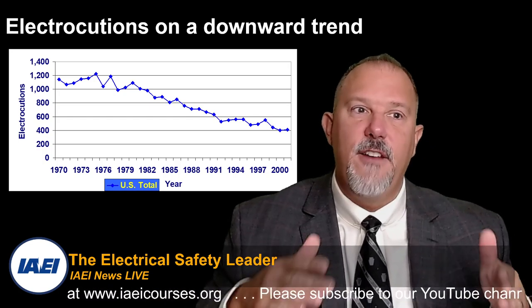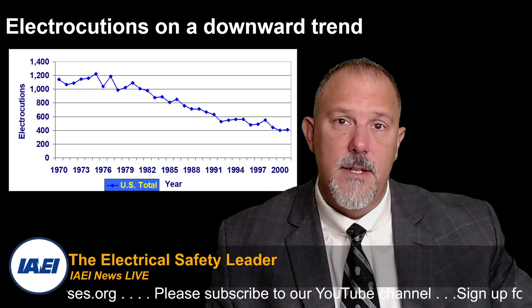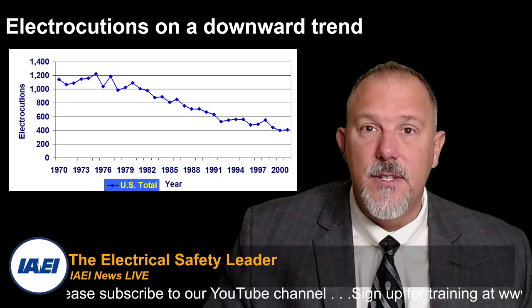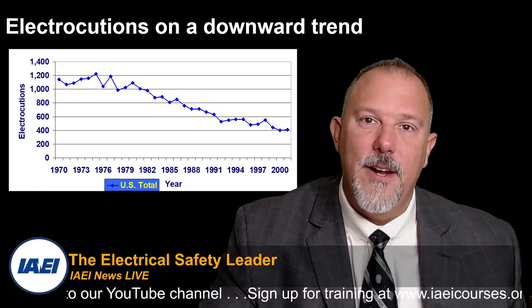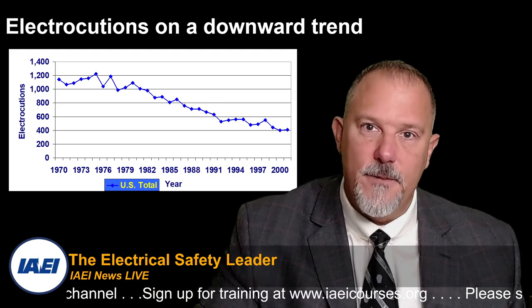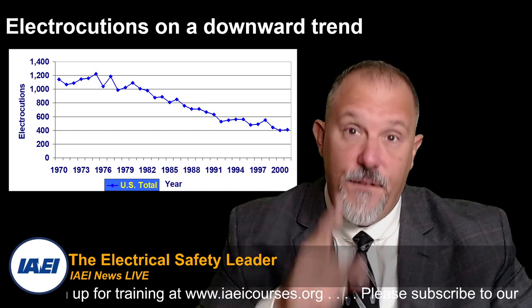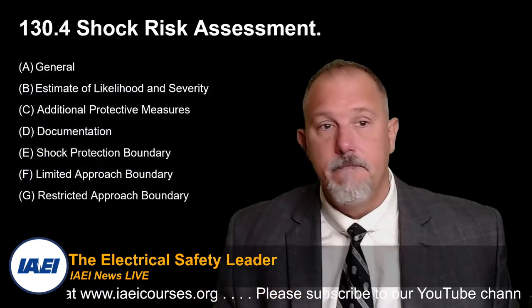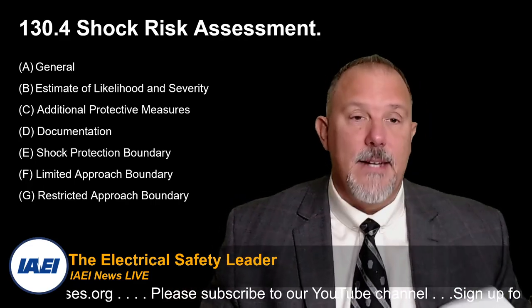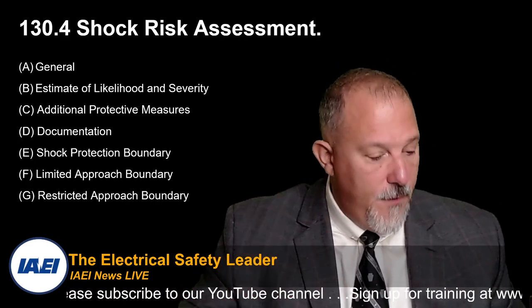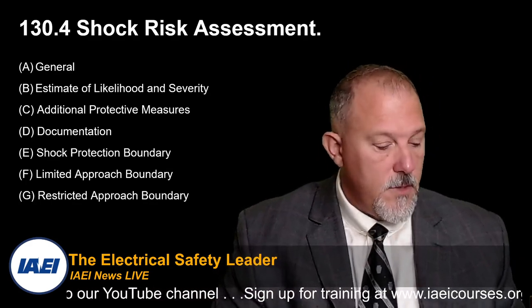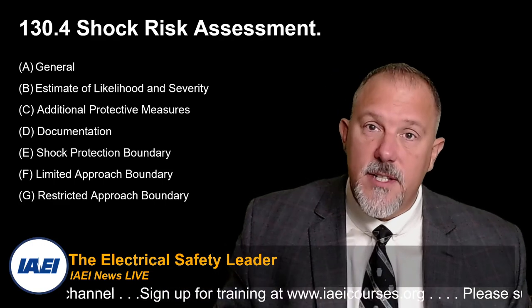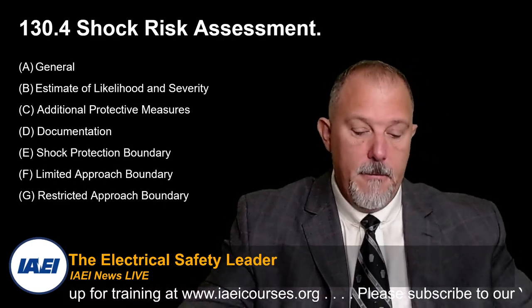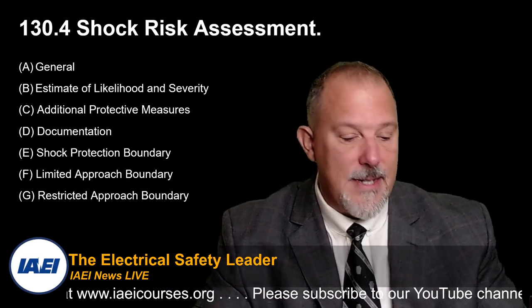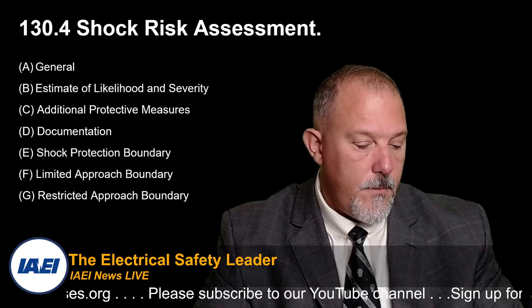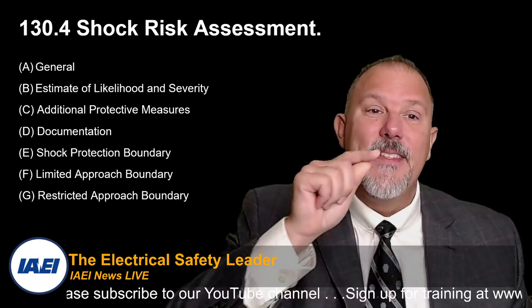The technologies have advanced considerably, both on the appliance side of the business and the circuit protection side of the business, and our awareness of electrocutions and shock. Anything 50 volts and higher, remember that. So what does NFPA 70E tell us? NFPA 70E tells us in 130.4, which is titled Shock Risk Assessment. Now remember, we have to do a shock risk assessment and we have to do an arc flash risk assessment. And if you look at the shock risk assessment, which is 130.4, there are general requirements. You have to estimate the likelihood and severity.